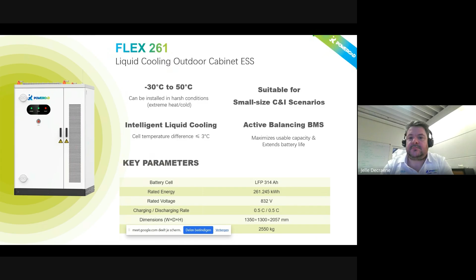This is then the 261 AIO all-in-one. The battery systems and PCS are fully integrated into a single cabinet, resulting in a very compact and simplified architecture. This is the new version using CALB LFP cells with the 314 ampere hour capacity, providing around 261 kilowatt hours of energy. Compared to the non-AIO version, this unit offers higher power capability with a rated power of 125 kilowatts and short-term peak power up to 137.5 kilowatts.